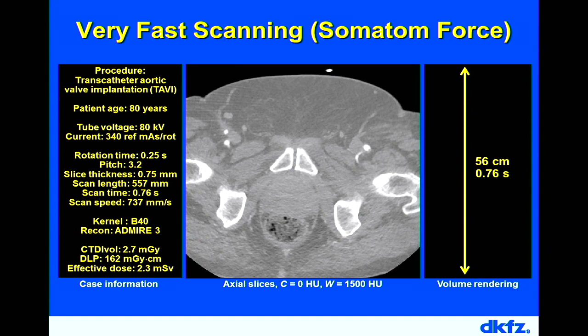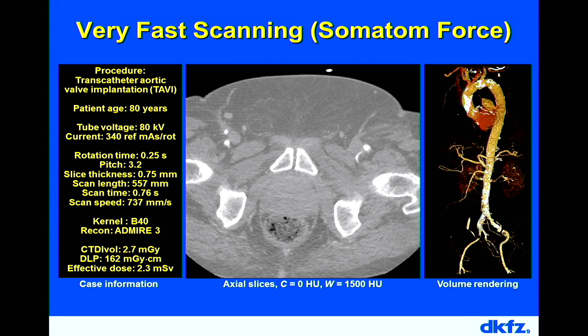A 56-centimeter scan range can be covered very fast — illustrated with the scan protocol, data acquisition view, and a volumetric display. Now why do we need cardiac CT specifically? The coronaries move with speeds up to 7 centimeters per second. If you want 0.5 mm spatial resolution, you need temporal resolution of around 5–10 milliseconds to freeze motion and avoid motion blurring. Even with today's fast CT systems, temporal resolution is not fast enough, so new ideas are needed.